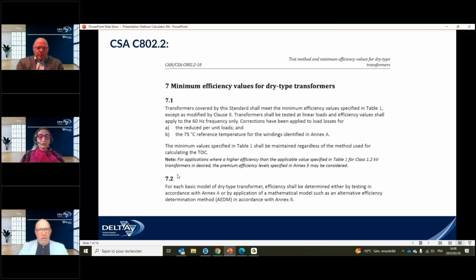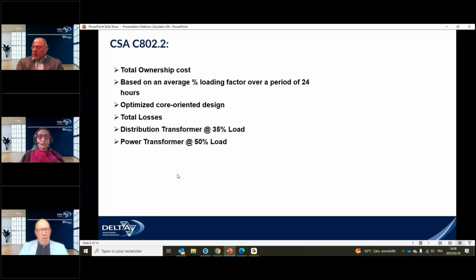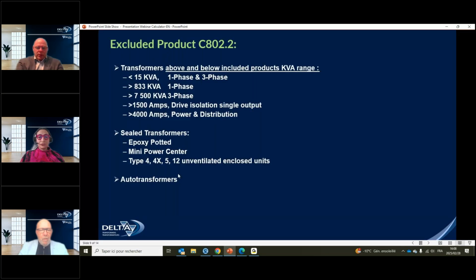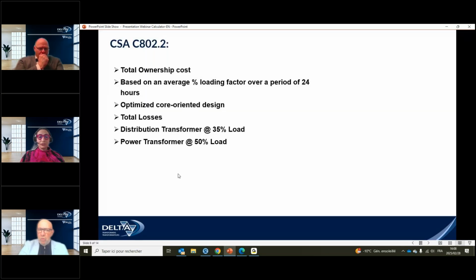That being said, depending on which type of transformer you have, the efficiency level is not necessarily the same. Just to give you an example, lower kVA transformers will require less efficiency than larger transformers. Low voltage transformers, 1.2 kV class and less, have to meet the efficiency level at 35% load. And power transformers, 2.4 kV class and above, have to meet the efficiency level at 50% load. That's the only point in all the efficiency curve that we have to comply with. So everybody's measured on that same level. Depending on the load level your product will be exposed to, your efficiency can be quite different. So that's the information that the tool will provide.